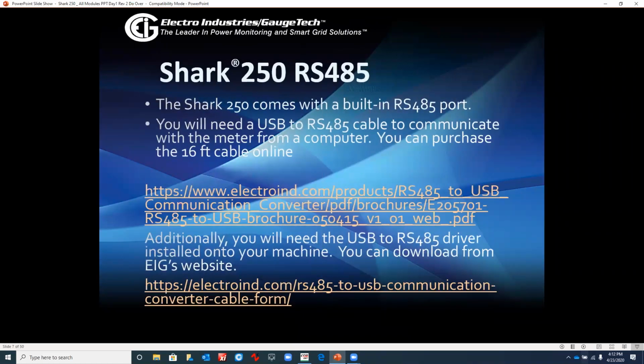Next, we have the Shark 250 RS-485 connection. And this comes with a built-in RS-485 port to the rear of the meter, as we took a peek earlier. You'll need a USB to 485 cable to connect to this meter. Typically, you can purchase this online from electroind.com, products, and so on. And this is a 16-foot cable. Again, you can purchase this online.